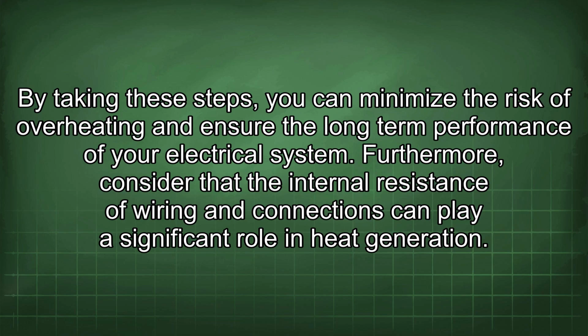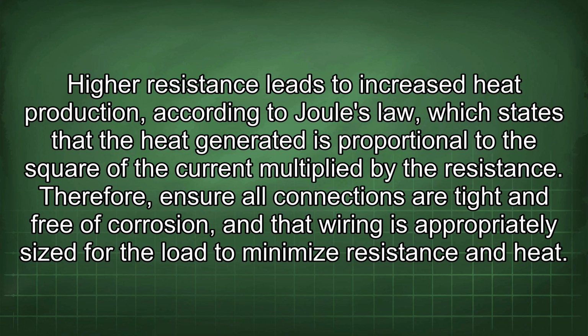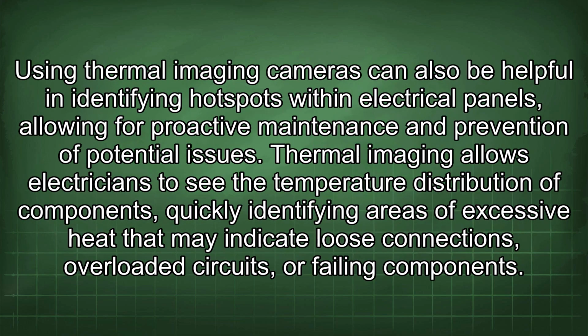of your electrical system. Furthermore, consider that the internal resistance of wiring and connections can play a significant role in heat generation. Higher resistance leads to increased heat production, according to Joule's law, which states that the heat generated is proportional to the square of the current multiplied by the resistance. Therefore, ensure all connections are tight and free of corrosion, and that wiring is appropriately sized for the load to minimize resistance and heat. Using thermal imaging cameras can also be helpful in identifying hotspots within electrical panels, allowing for proactive maintenance and prevention of potential issues.